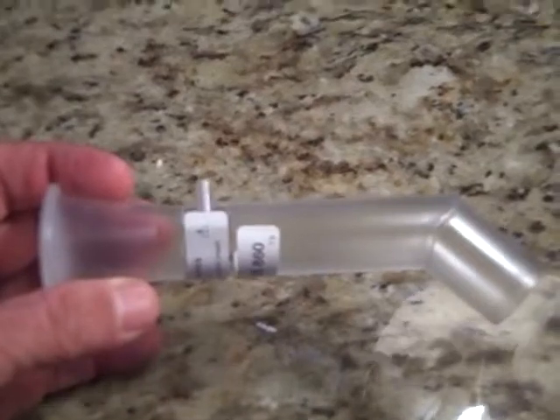This is a little better picture of the tube that we use for the calibration and for the actual test. There is a number, probably a little hard to see here. It says cal, and then there's a number on here that we have to enter into the calibration syringe. As you can see here, this is the power cable and the connector to the printer that's hooked up to the rear of the cradle that the spirometer sits in. As you can see here, these are the two connectors for the power cord and for the cable on the back of the printer.